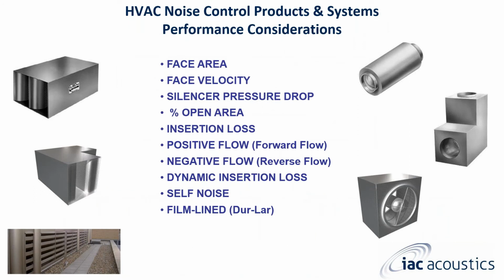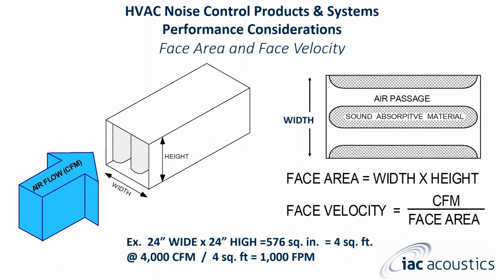We're also going to now cover face area, face velocity, silencer pressure drop, percent of open area, insertion loss for reverse flow, dynamic insertion loss, self-noise, and then we'll also touch on our film-lined silencer, nicknamed our hospital grade. Face area and face velocity.